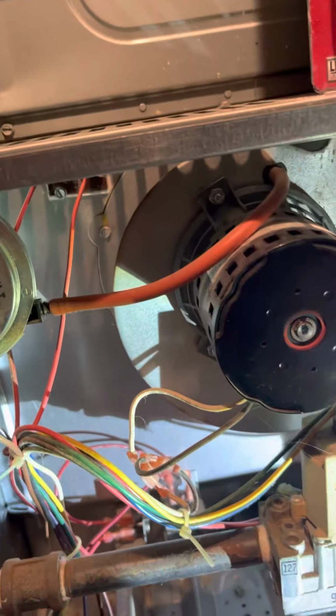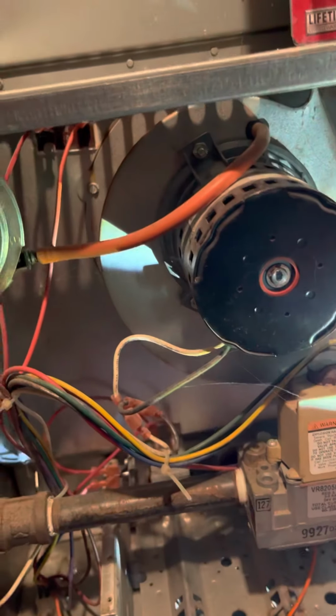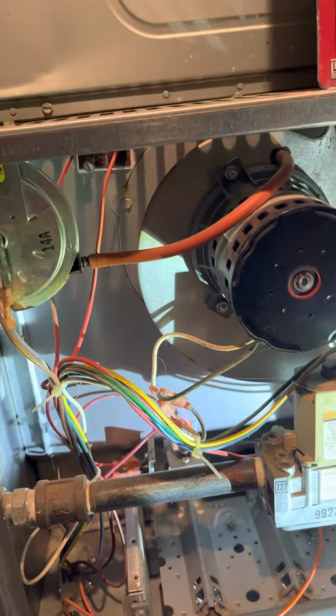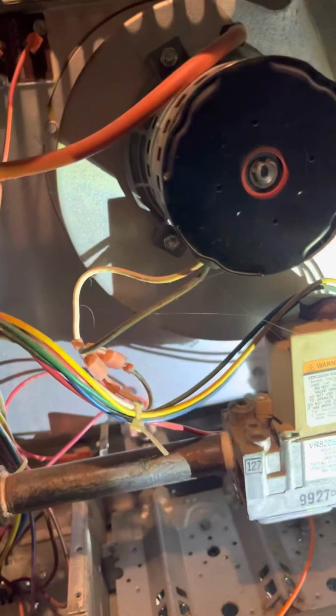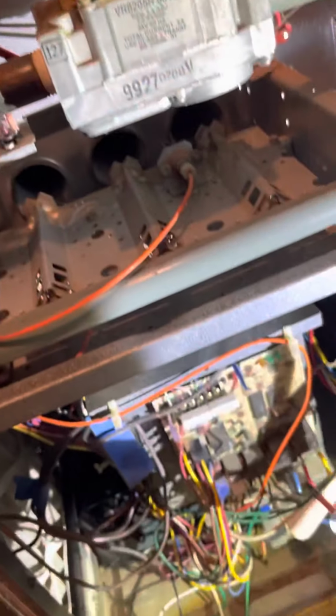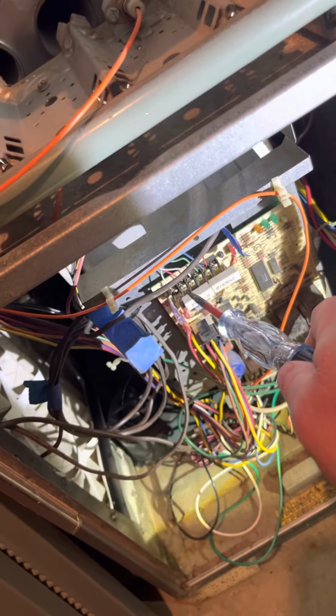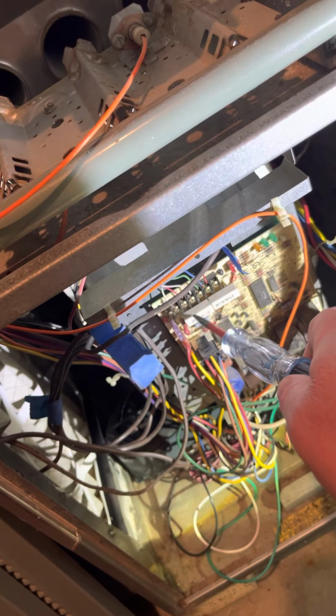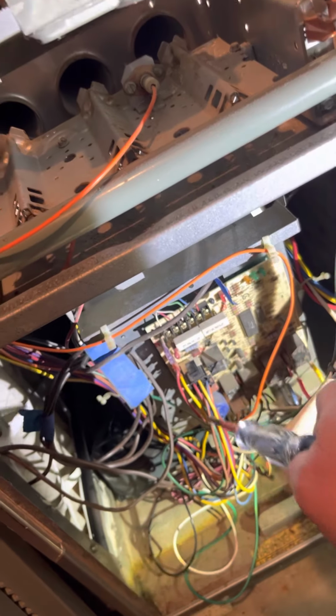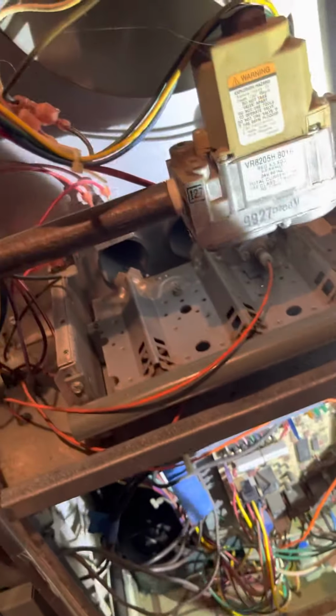Then you can get your tester out. You can do an ohm test on it, or you can check for 24 volts. You can use this tester and go to your fuse and check on both sides of your fuses to see if you have power. You can touch R, you can touch W, you can touch Y in cooling, and it's going to light up if there's 24 volts there.